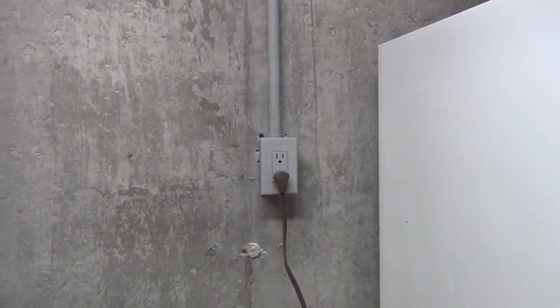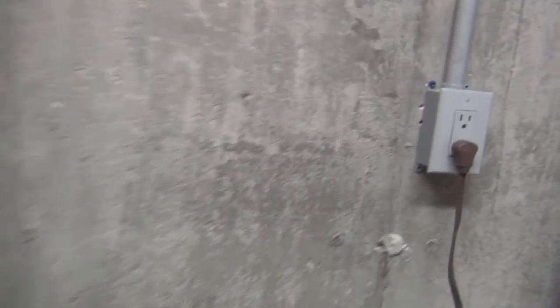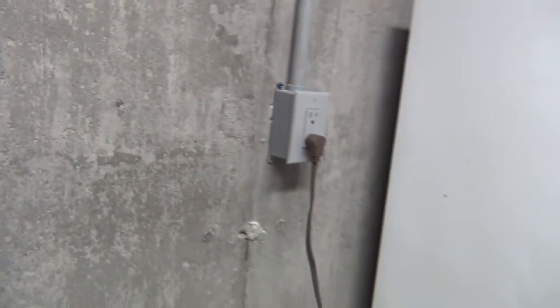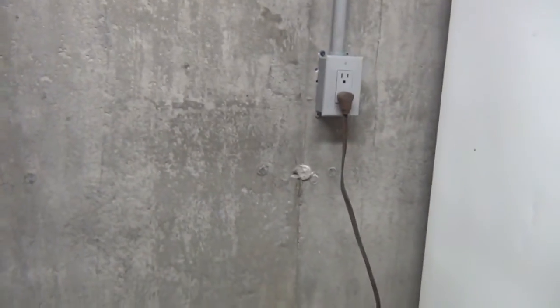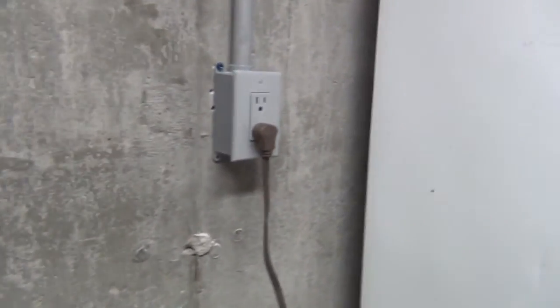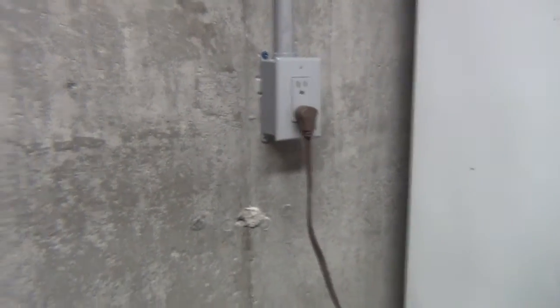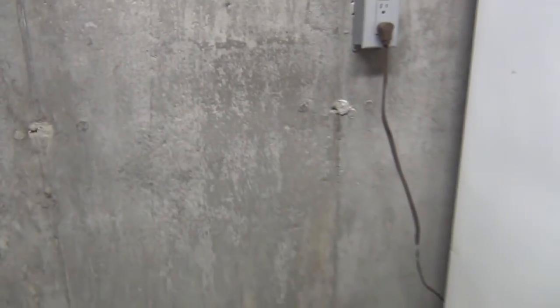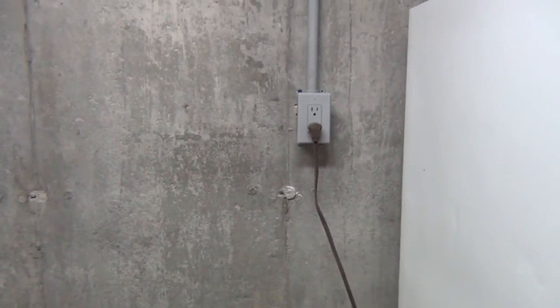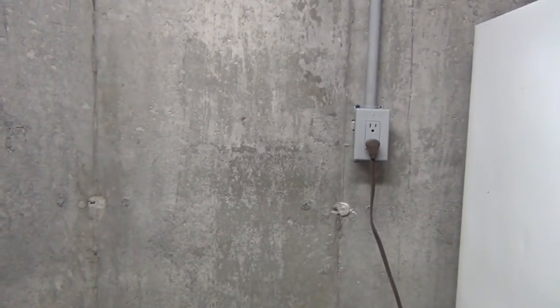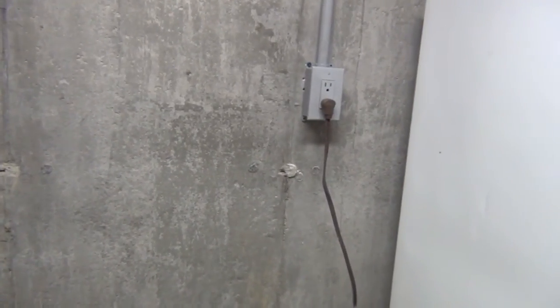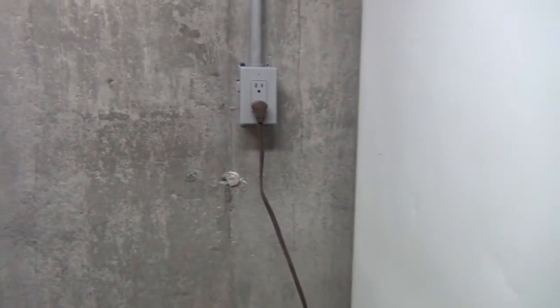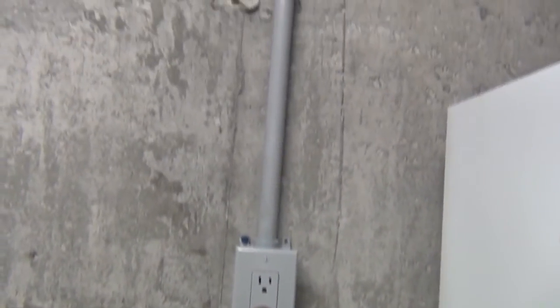if you've ever noticed metal boxes that have been mounted onto concrete when electrical work is done, come back in about five, ten years and take a look at that metal box. It is going to be a rusted, corroded mess, because, obviously, concrete is always moist and curing over time. It's going to react with that metal, and it's going to look horrible when all of a sudden, if you ever have to get into that box to do any work, the screws are going to break. It's going to be a corroded mess.